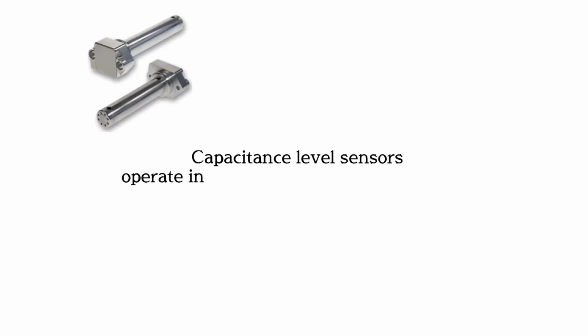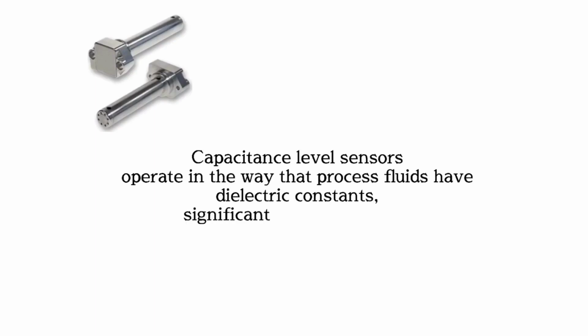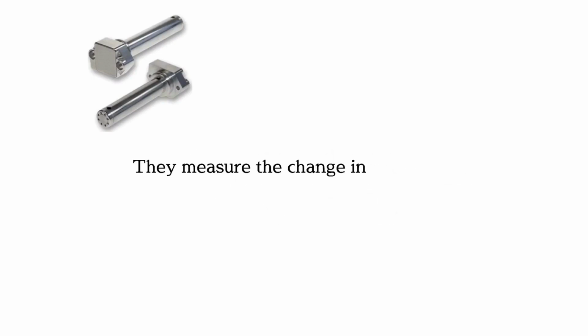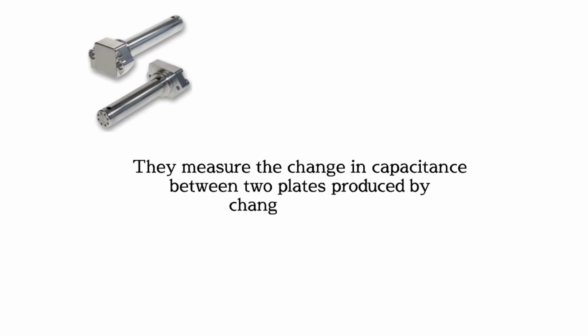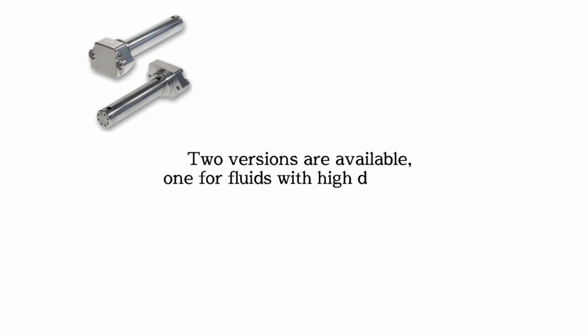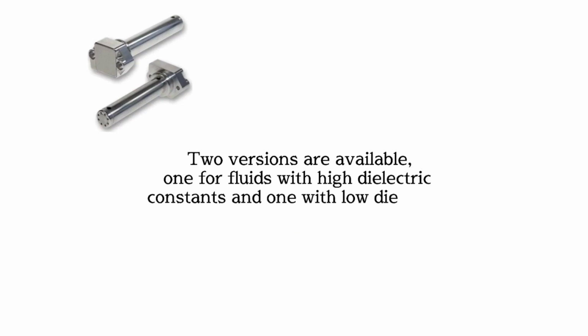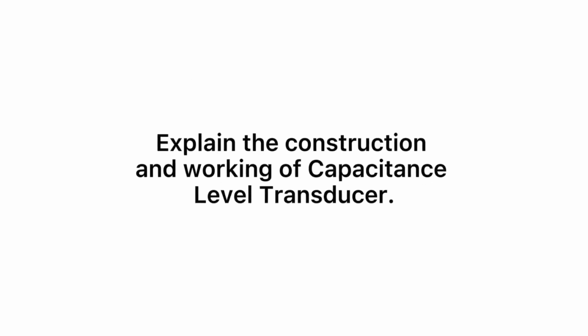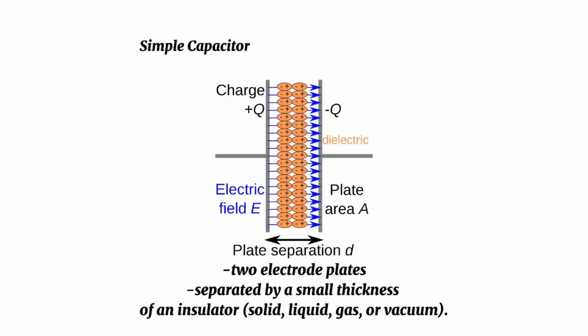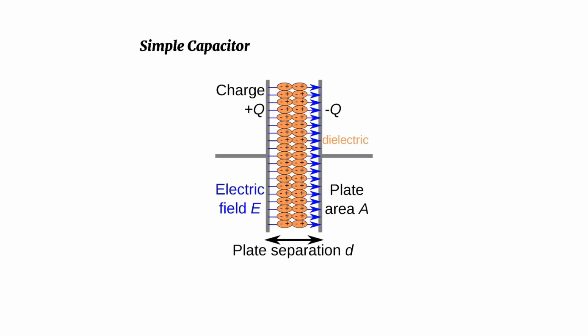Capacitance level sensors operate in the way that processed fluids have dielectric constants significantly different to air. They measure the change in capacitance between two plates produced by changes in level. Two versions are available, one for fluids with high dielectric constants and one with low dielectric constants. A simple capacitor consists of two electrode plates separated by a small thickness of an insulator, such as solid, liquid, gas, or vacuum. This insulator is also called the dielectric.